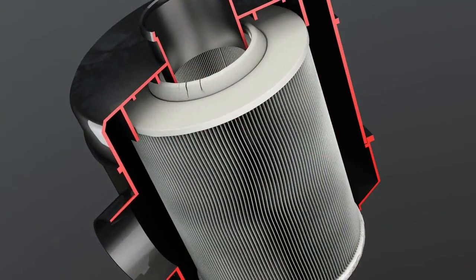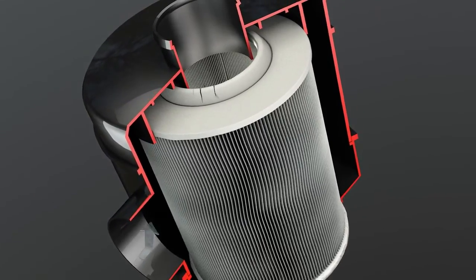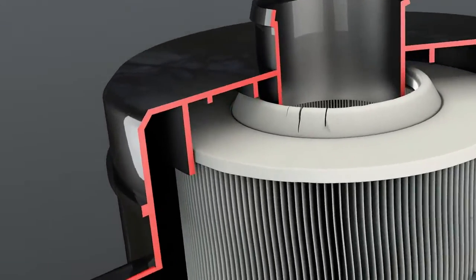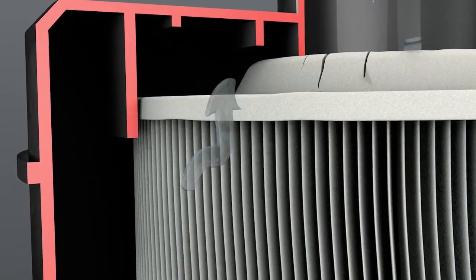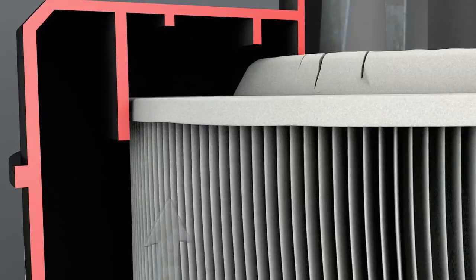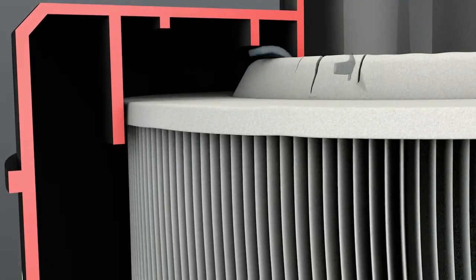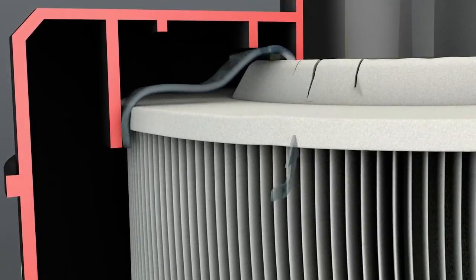Some non-genuine filters can cause more problems than they prevent. Unsuitable seals may result in holes, grooves or cracks. In many cases the seal has no chance of doing its job because the filter is not fitted exactly to the dimensions of the housing.